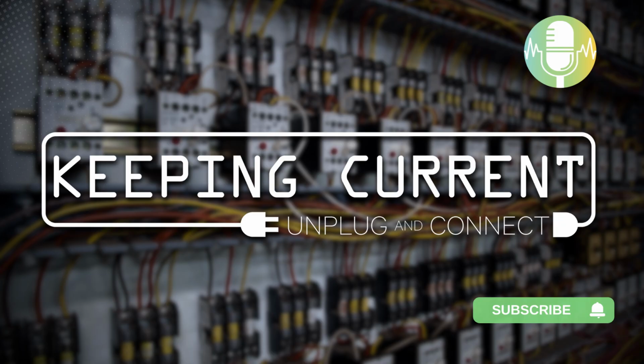That's a 3 kilowatt hour power swing almost instantaneously, which checks off the power quality issues we discussed earlier with the grid. That allows us to handle fast changing loads. AI data centers have fast changing loads, peaks and valleys that really aren't predictable, so these systems are the buffer between the grid and the data center. It also opens the door for things like frequency regulation and ultra rapid peak shaving, things we used to dream about with traditional electronics that are now a reality with these new inverters and batteries.